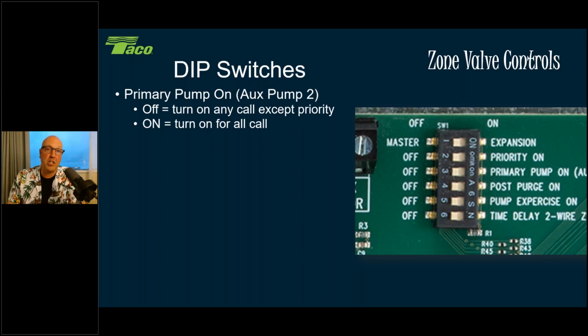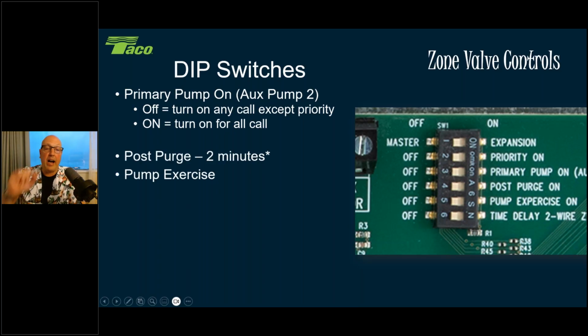So the first 3 dip switches are the same between the SRs and the ZVCs, as well as post purge and pump exercise. And then you'll also see, now I'm sorry, post purge on a zone valve board is slightly different than the switching relay. The switching relay, we keep it to the last zone that was calling. We put the BTUs back into that zone.